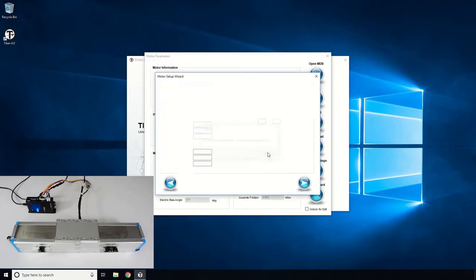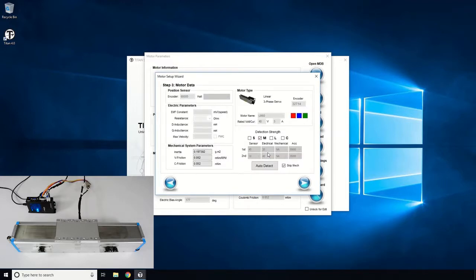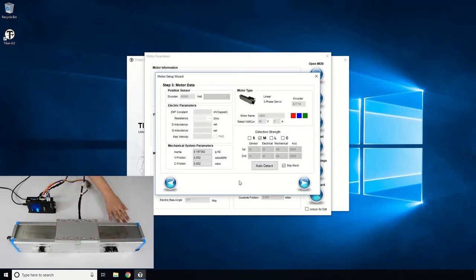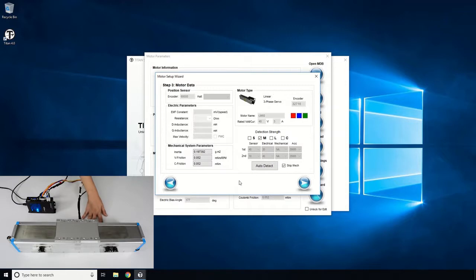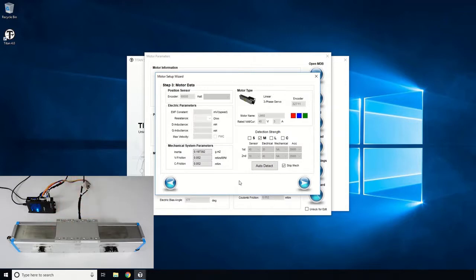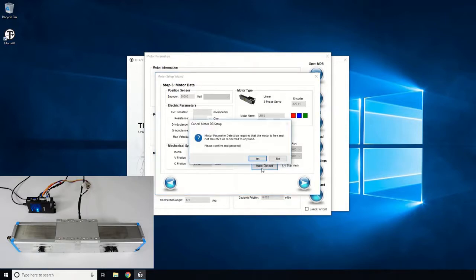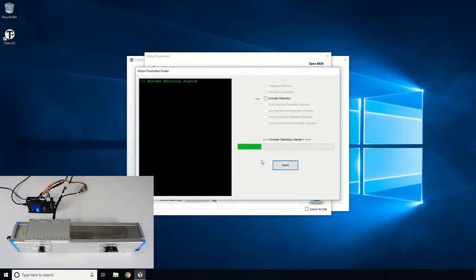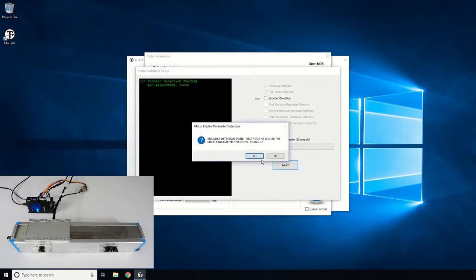Before we perform the auto detection routine, please make sure the motor does not have any load and is held down or mounted on a stable location. Let's place the motor stage in the middle of the stroke. Select the Auto Detect Sequence button and start the auto detection routine. First, the motor will go into motion to find the encoder direction polarity in respect to the motor phase.